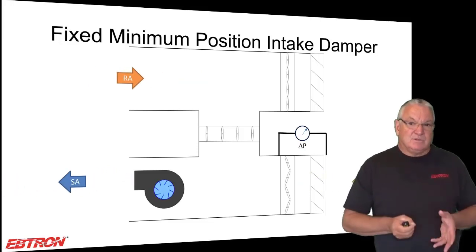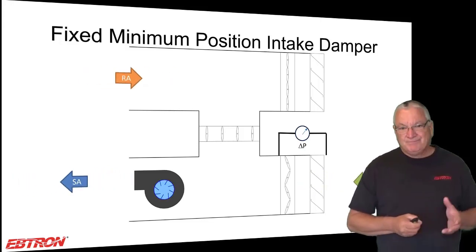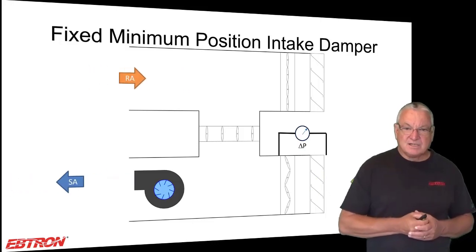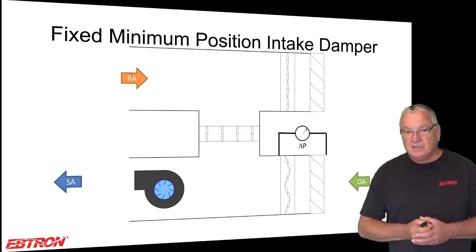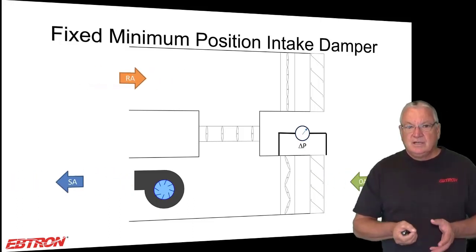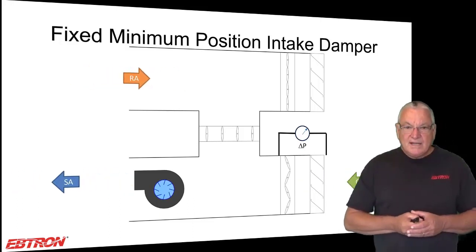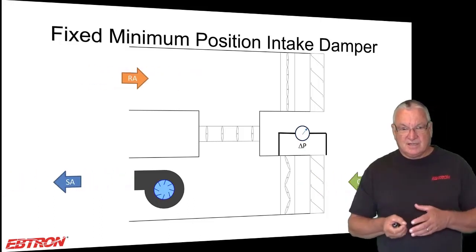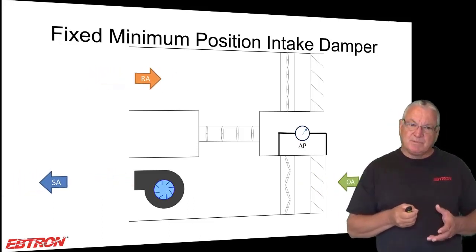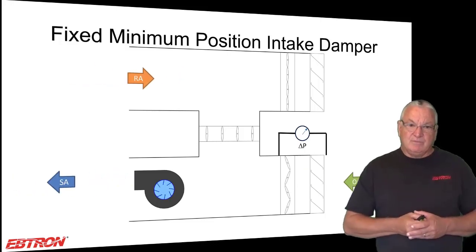And it's real simple. If you look at that lower right-hand part of the slide, I have a louver and I have a fixed damper. So it's a fixed orifice, right? So what ends up happening is I have a certain pressure drop across it that's associated with the supply fan volume of air.